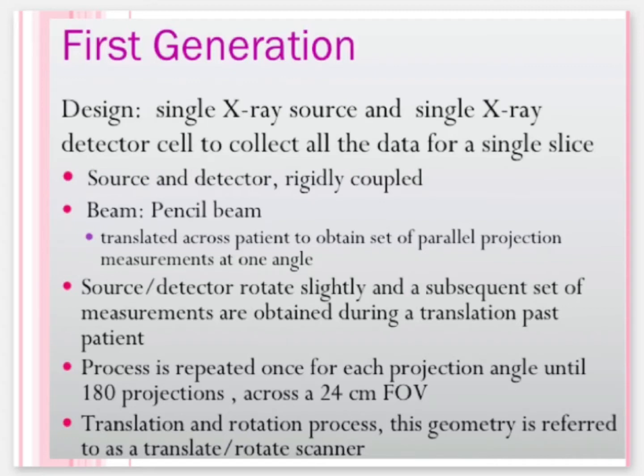Pencil beam translated across the patient to obtain a set of parallel projection measurements at one angle. The source-detector then rotates slightly, and a subsequent set of measurements are obtained during a translation past the patient.